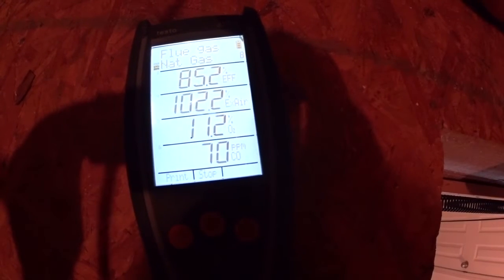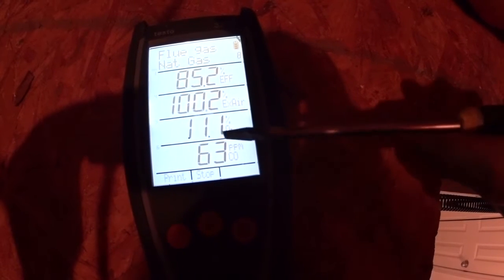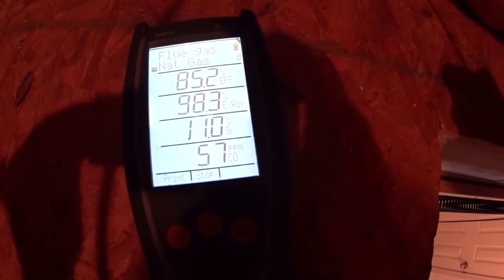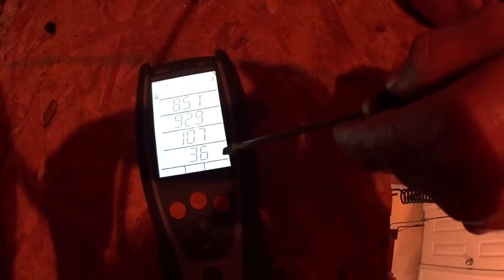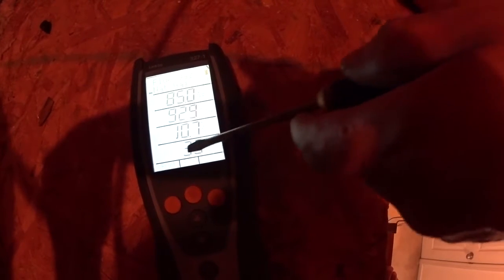You want this between six and nine, you want this between six and nine, below 100 CO — carbon. Now remember you have your initial ignition, but after your ignition you're going to have your initial spike, but after that spike you should never see it rise.